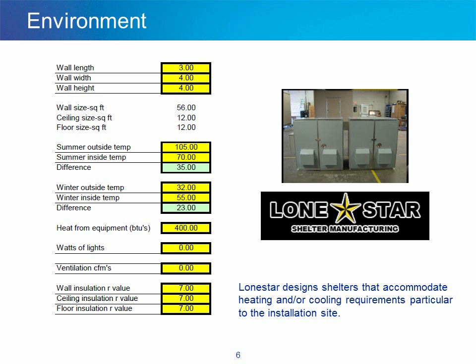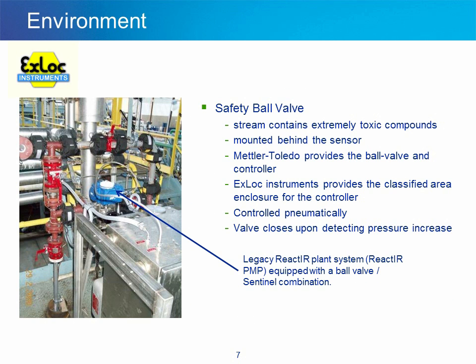Lone Star will design shelters that accommodate heating and/or cooling requirements particular to the installation site. In cases where the analysis stream contains extremely toxic compounds, a safety ball valve may be required, mounted behind the sensor. Mettler Toledo provides the ball valve and controller, and ExLoc Instruments will provide the classified area enclosure for the controller. The ball valve is controlled pneumatically. If an increase in pressure is detected behind the sensor, the valve closes, preventing liquid from entering the optical conduit opening. Shown here is a legacy React-IR plant system, a React-IR PMP, equipped with a ball valve-Sentinel sensor combination.